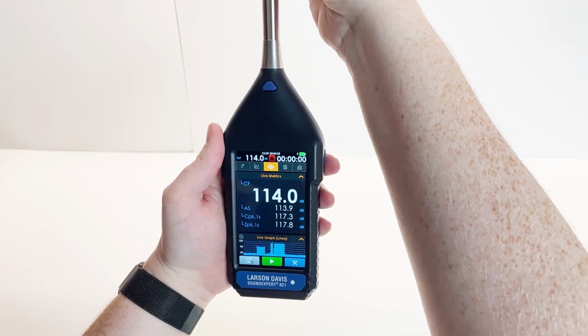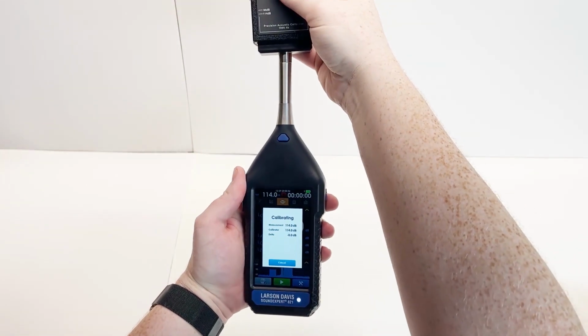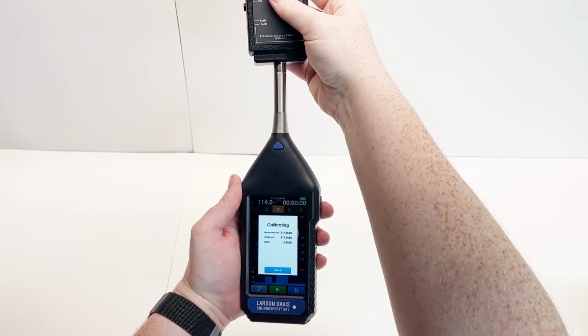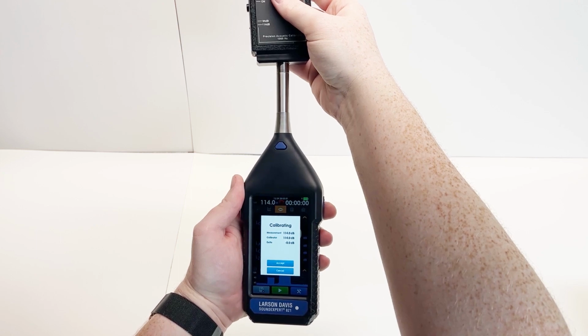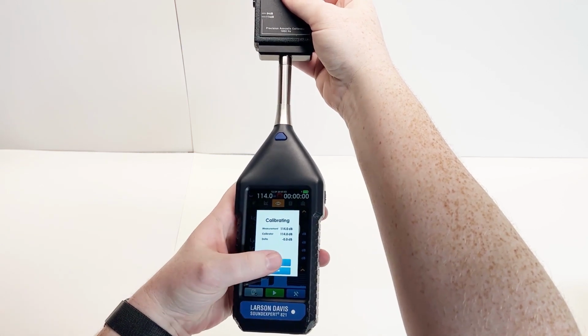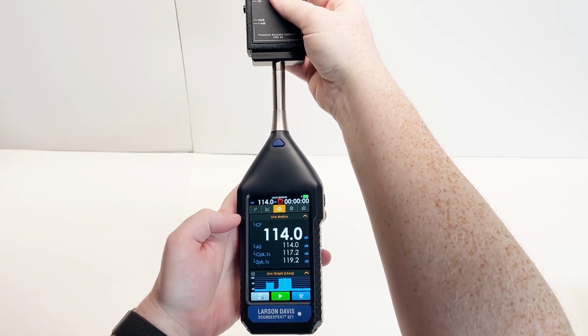If that still doesn't work, ensure that the calibrator is seated correctly on the microphone. I also recommend changing the battery in the calibrator, as a low battery can produce a lower than expected calibration output level.